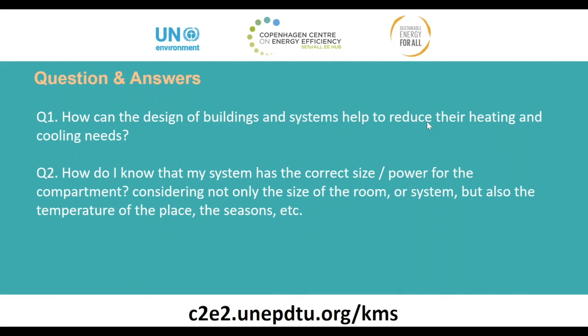When it comes to active systems, you can know if you have the correct size or correct power consumption. In the case of power, you can measure through power analyzers, or you should be able to see that value on your digital electrical panels for that particular component. So compare it with your rated design power. If the operating power is close to the design values, then the system sizes are quite acceptable. If it is way too high, then you are overloading the system. At times that means your systems are designed for a lower capacity and you are overusing them.